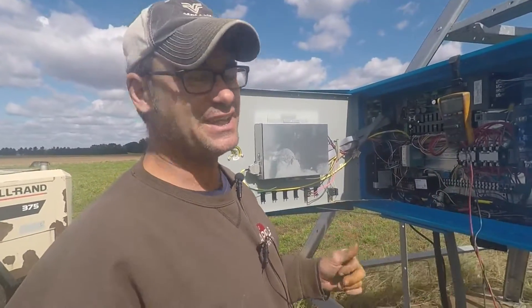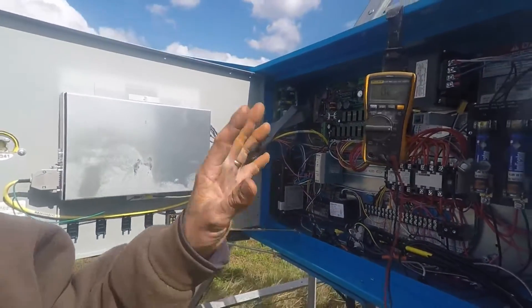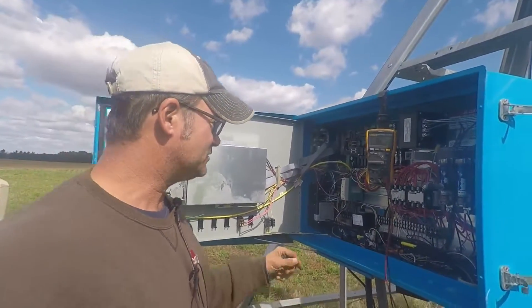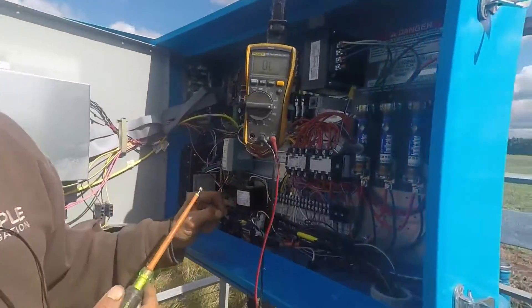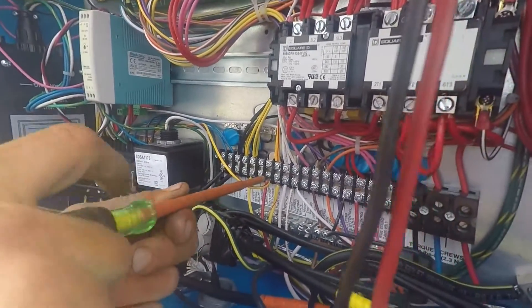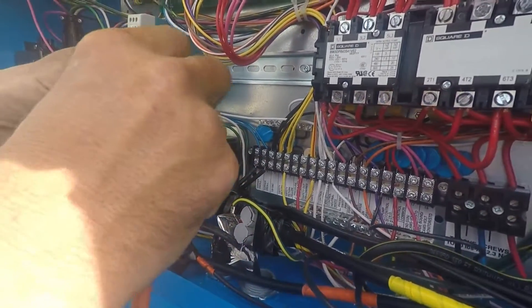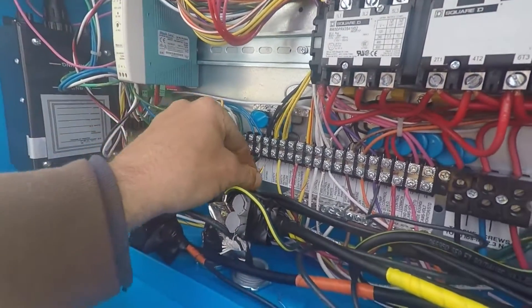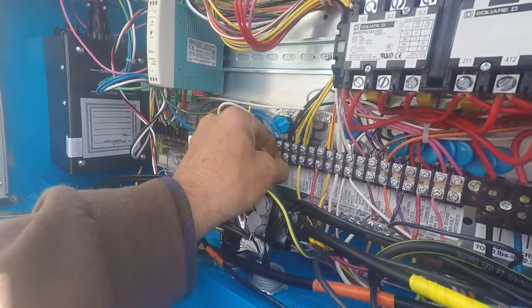However, we could have a bad oscillator. The oscillator should be putting out somewhere between three and a half and seven volts when the machine is operating. So to test the oscillator we have to hotwire it. We're going to take the wire that normally runs the oscillator and we're going to move it onto 120 volts AC. Now the oscillator will be powered continually whenever the disconnect is on.